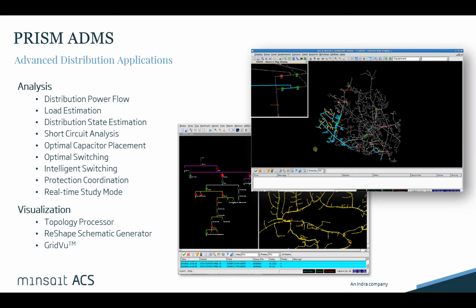As the term analysis implies, these don't perform real-time changes to the system. They're used by dispatchers to analyze the current state of the network, whether that's short circuit analysis to locate faults, or determining optimal capacitor placement. We'll talk about optimal intelligent switching in a moment. Protection coordination permits evaluation and coordination of curves on protected devices on the circuit, and real-time study mode permits operators to evaluate actions on the system without actually performing them in the field.